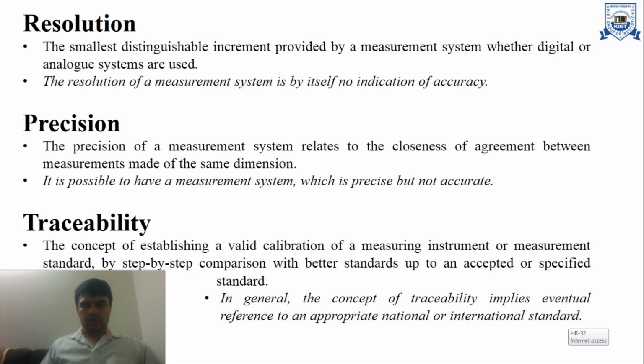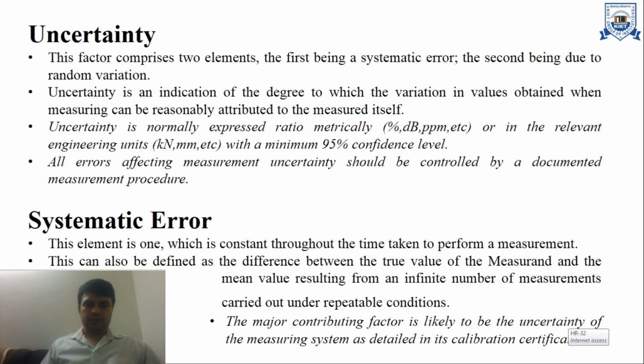Then traceability. This is the concept of establishing a valid calibration of a measuring instrument or measurement standard by step comparison with better standards up to an accepted or specified standard. In general, the concept of traceability implies eventual reference to an appropriate national or international standard. It means that in this case we have to take the reference of national or international standards for our measurement, and we have to trace according to that.